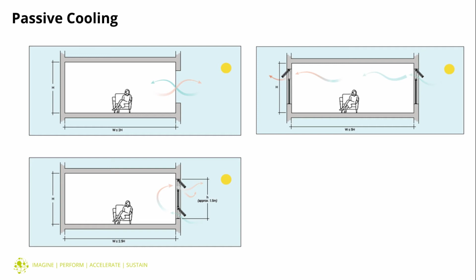One thing that's key to making sure this strategy has its maximum impact is understanding what we mean by an opening. When we size these natural ventilation openings or windows, we need to make sure we're talking about the same thing — the actual area that is open to the outside, not just the physical area of the window, but how much it actually opens, the area that's exposed to the outside air.